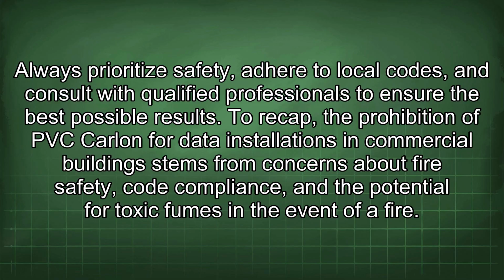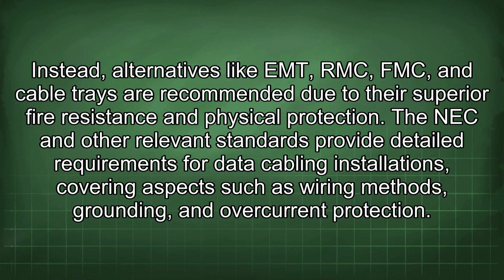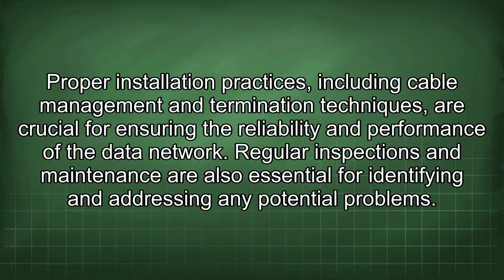To recap, the prohibition of PVC Carlon for data installations in commercial buildings stems from concerns about fire safety, code compliance, and the potential for toxic fumes in the event of a fire. Instead, alternatives like EMT, RMC, FMC, and cable trays are recommended due to their superior fire resistance and physical protection. The NEC and other relevant standards provide detailed requirements for data cabling installations, covering aspects such as wiring methods, grounding, and overcurrent protection. Proper installation practices, including cable management and termination techniques, are crucial for ensuring the reliability and performance of the data network. Regular inspections and maintenance are also essential for identifying and addressing any potential problems.